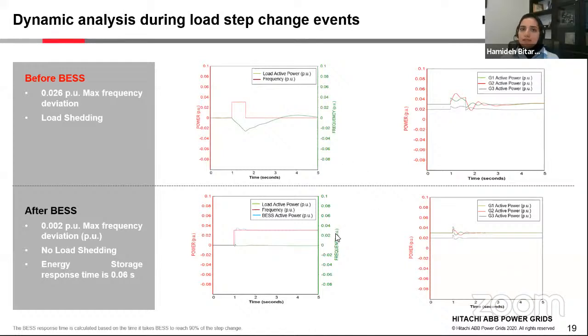So what happens if we add the energy storage? As you can see, the energy storage responds to this contingency and provides a prompt response to supply the additional load. It also significantly reduces the frequency excursion and avoids load shedding. These are the main benefits of integrating BESS for load step changes.